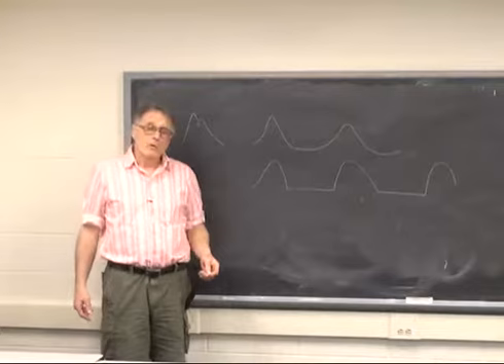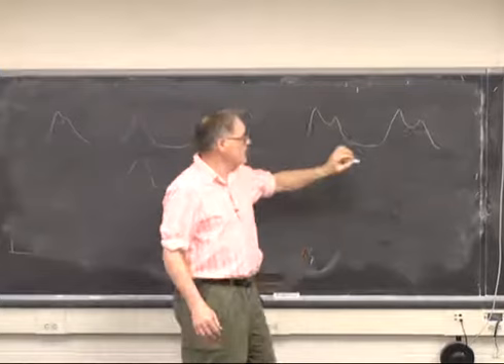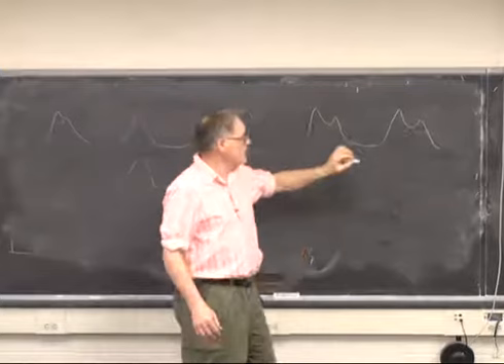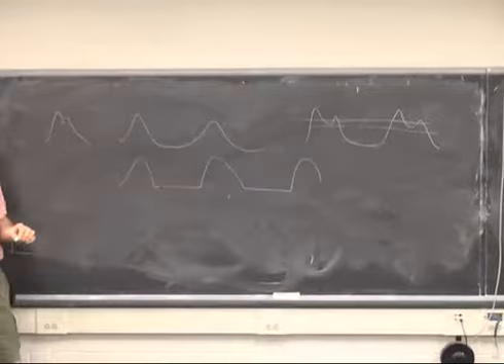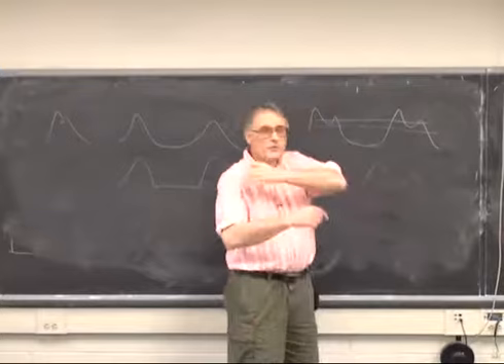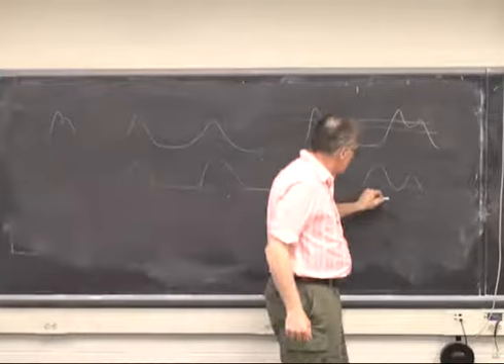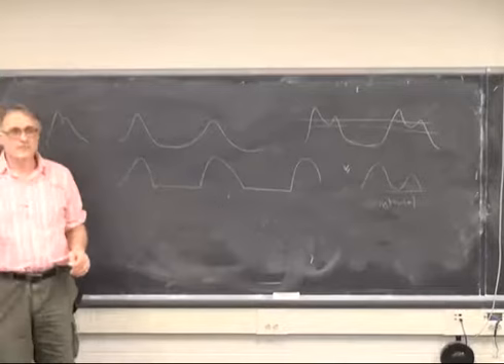If you have a fairly strong dicrotic notch — some very amplified waveform — then clearly if you're going to have a threshold for determining what is a pulse, you want to make sure you set the threshold above the notch and not at its level. Because otherwise you'll get pulse doubling. Your software should be able to detect that because if you have pulse doubling, you're going to find a bimodal histogram in terms of intervals.